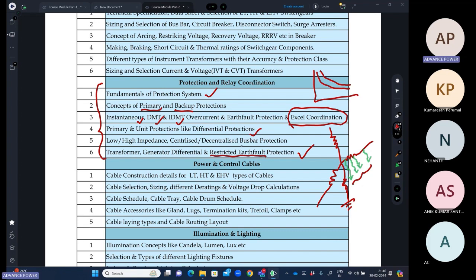Then for bus bar, we'll discuss the low and high impedance protection. So it will be centralized or decentralized, how we select these systems, how the high impedance protection is selected, and at which place, like for REF, we select the high impedance. For other differential protection, we use the low impedance.